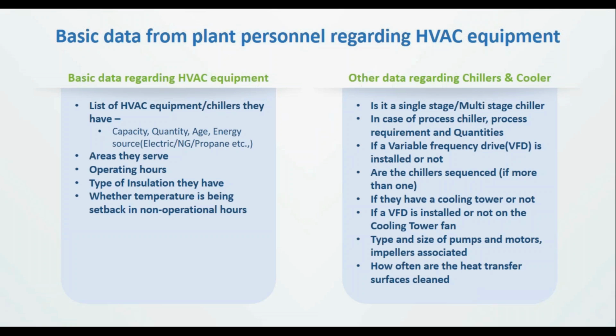So we try to get an idea about the chiller operating profile and the pipe insulation and the load, and we do some measurements as well to be able to ascertain these parameters. But what we do is mostly on the day of the assessment, and it's probably going to be a snapshot type of measurement, maybe over a few hours. But I think what would benefit the HVAC system and the chillers would be a more continuous measurement and trying to look at the efficiency over time, which I think would be very beneficial on the continuous improvement level. Next slide.